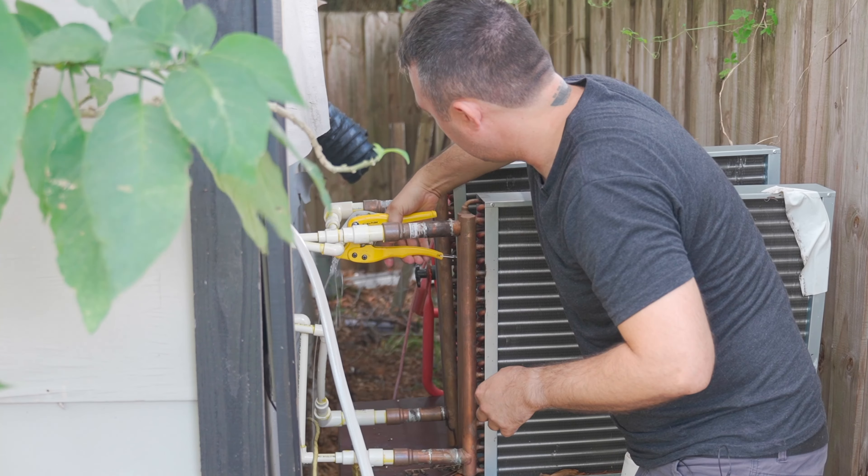We've got this S19J Pro in the tank I got from Engineered Fluids. In this acrylic tank, the fluid that comes out of the discharge is going to go into the pump. From the pump, it's going to run through the heat exchanger, then back into the tank. The dielectric fluid loop is literally just: out of the tank, through the pump, through the heat exchanger, back into the tank. That's the only place there is dielectric fluid — the only place there's oily fluid.